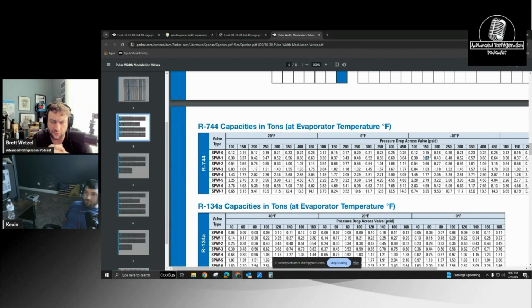I thought those are only usually 2,900 BTUs. They are, but it had a 4-ton valve on it. Oh, that's silly. We went from a number 4 Danfoss to a number 1 Danfoss. Damn. Yes, it would hit, and then 30 seconds later, the rack would just wash out. Is that the one where you called me and said, man, I've never seen a rack suction this white? Yeah, it would literally run for a minute, and then it would just flood back instantly.